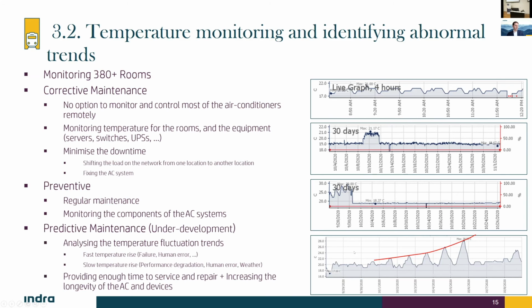Why does it happen? There are two different trends. You can have a fast temperature rise, which can be due to a failure in a component, or human error - like a technician who goes into the room, feels cold, and turns off the air conditioner or changes the temperature. Or it can be a slow rise, like in this example, which can be due to performance degradation, or again human error - someone sets a wrong set point for the air conditioner - or it can be because of weather.